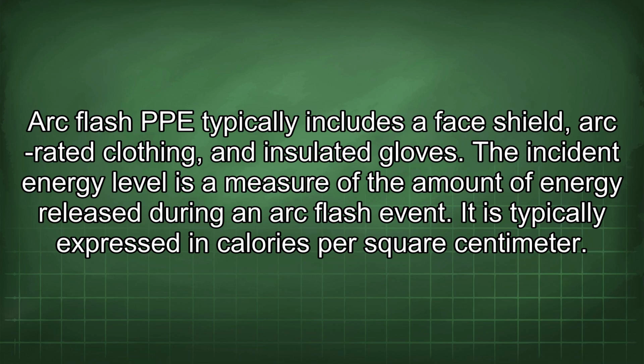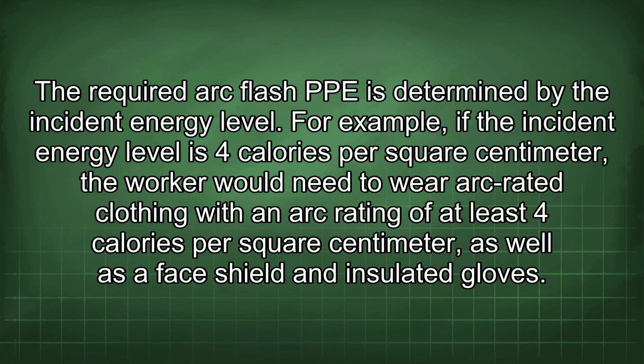The incident energy level is a measure of the amount of energy released during an arc flash event. It is typically expressed in calories per square centimeter. The required arc flash PPE is determined by the incident energy level.